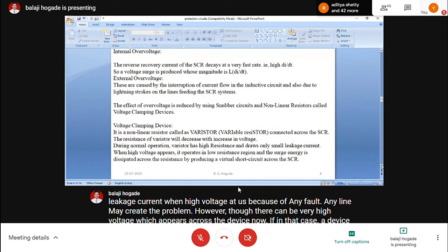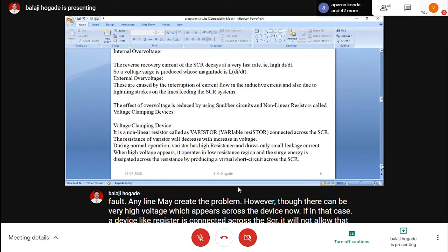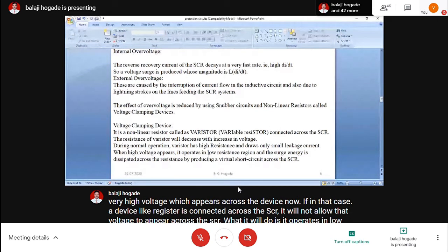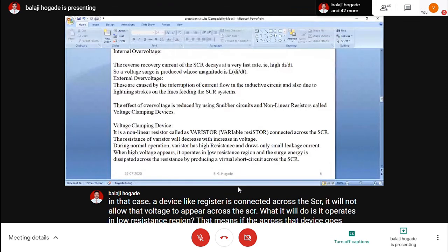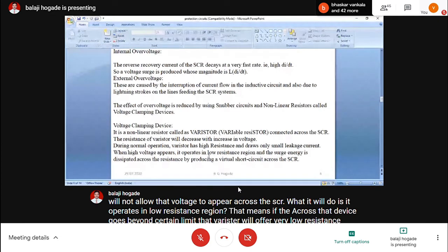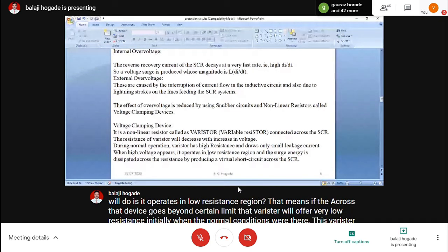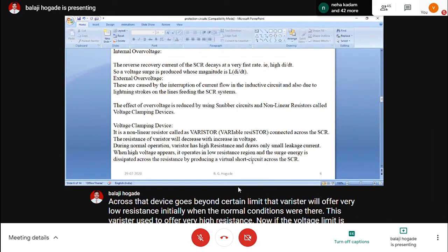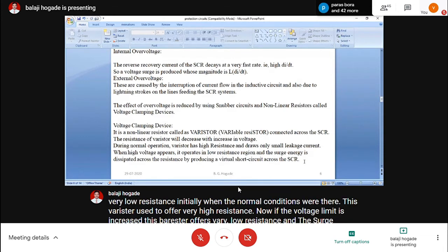What it does is operate in a low resistance region. That means if the voltage across that device goes beyond a certain limit, the varistor will offer very low resistance. Initially, under normal conditions, this varistor used to offer very high resistance. Now, if the voltage limit is increased, the varistor offers very low resistance, and the surge energy is dissipated across the resistance by producing a virtual short circuit across the SCR.